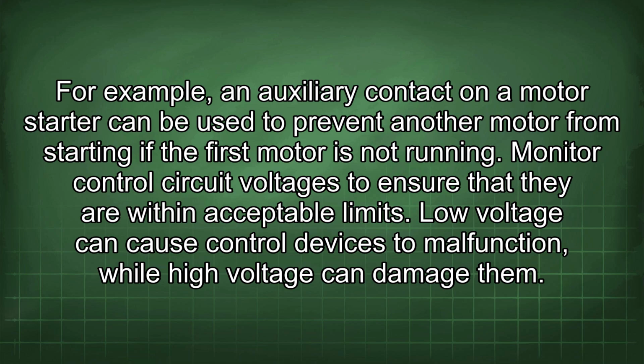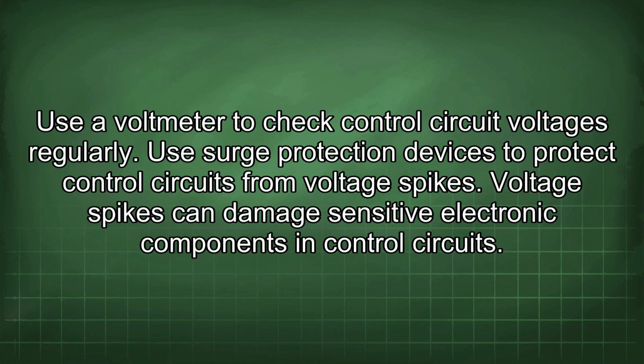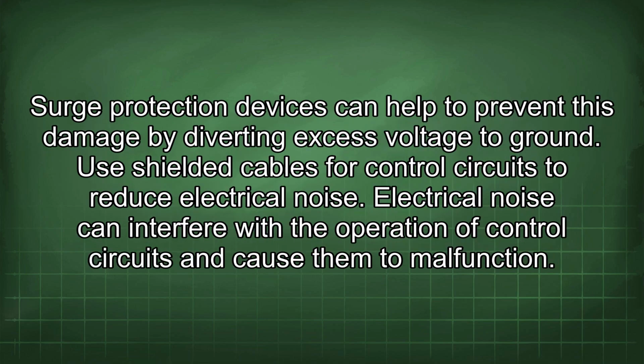Monitor control circuit voltages to ensure that they are within acceptable limits. Low voltage can cause control devices to malfunction, while high voltage can damage them. Use a voltmeter to check control circuit voltages regularly. Use surge protection devices to protect control circuits from voltage spikes. Voltage spikes can damage sensitive electronic components in control circuits. Surge protection devices can help to prevent this damage by diverting excess voltage to ground.